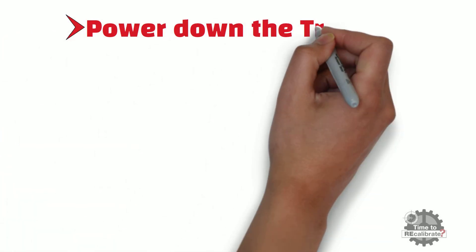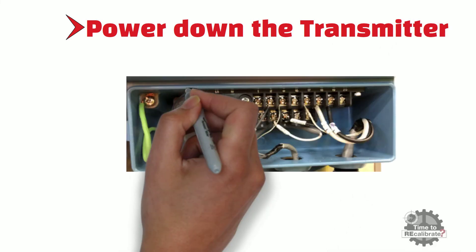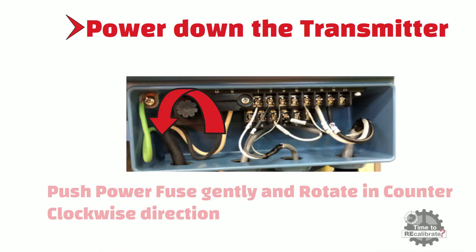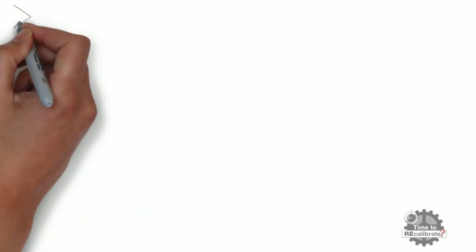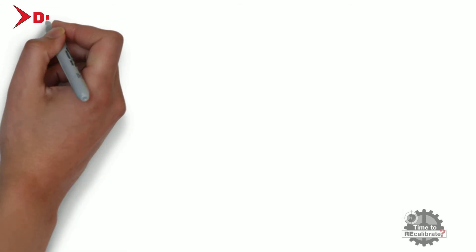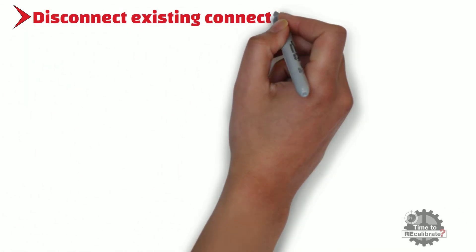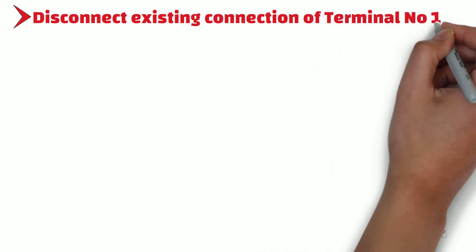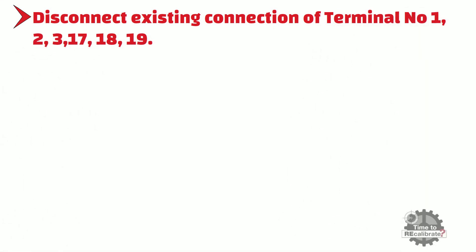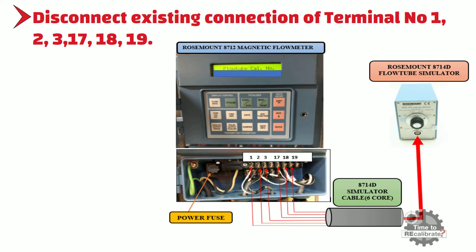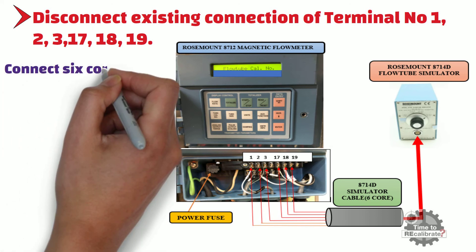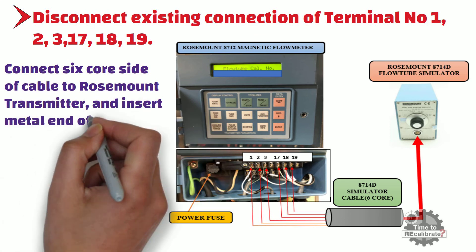Step 5: Power down the transmitter. Push the power fuse gently and rotate it in the counterclockwise direction. Once power is off, disconnect the existing connections on terminal numbers 1, 2, 3, 17, 18, and 19. Make sure that power is off when you disconnect the cable from the transmitter. Now connect the 6-core side of the cable to the Rosemount transmitter, and insert the metal end of the wiring assembly into the calibration standard.